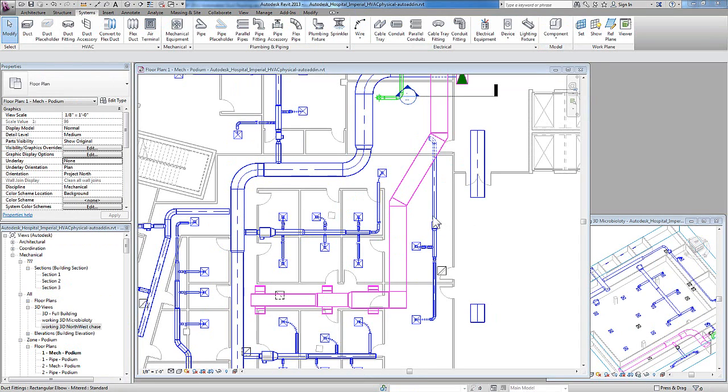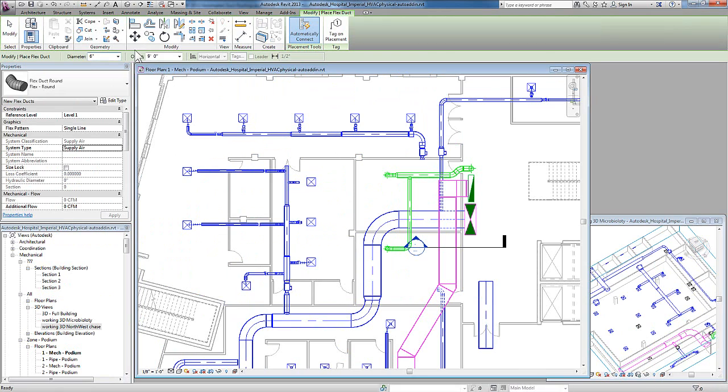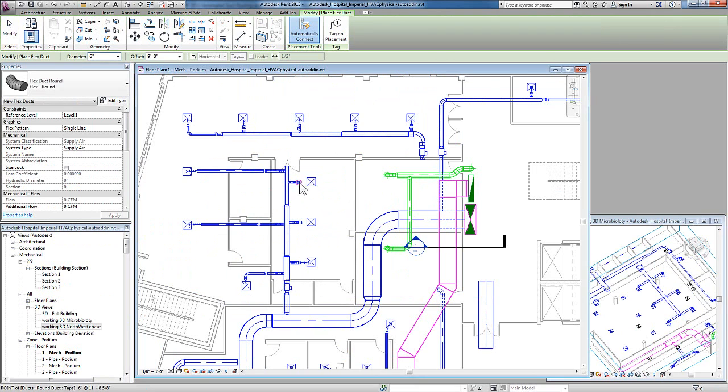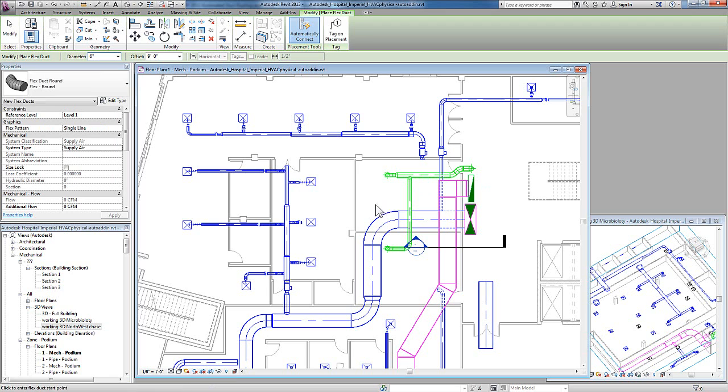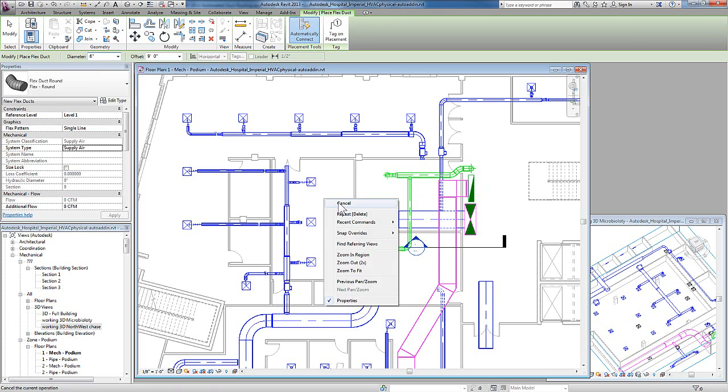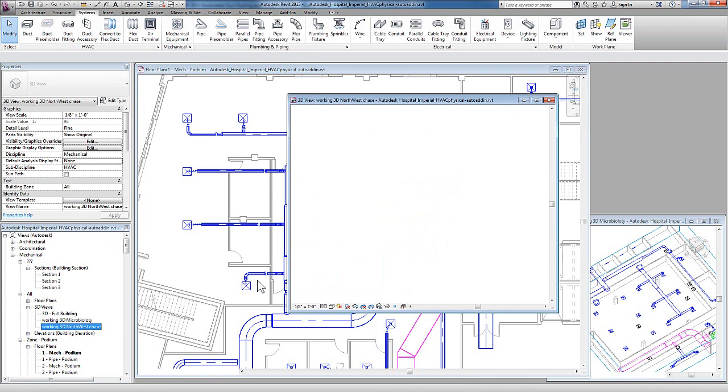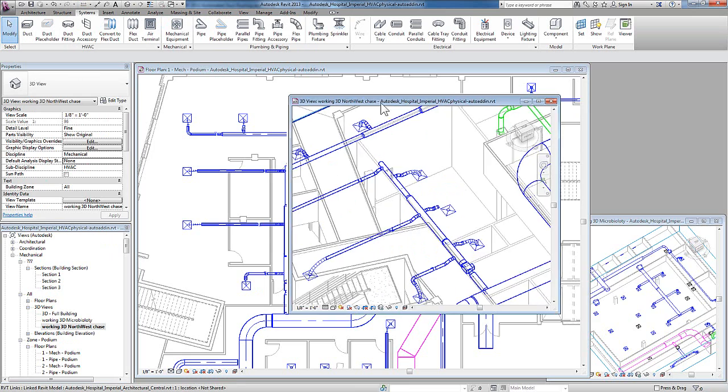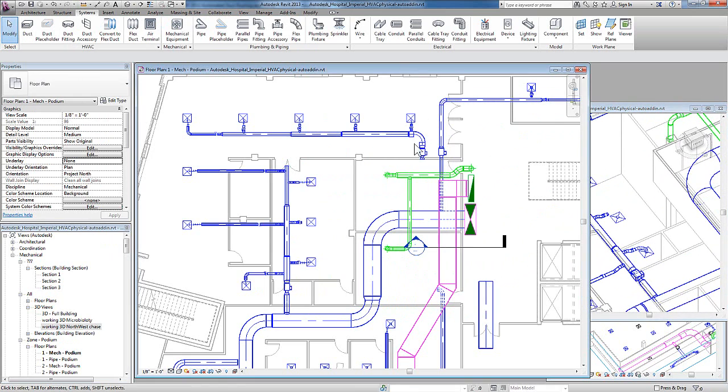If I want to manually add in flex ducts, I can use the flex duct tool and verify that the system type is correct and hover my cursor over the end of a duct, making sure that I'm hitting the connection point. Once I pick the connection point on the duct, I can pick the connection point on the terminal and the flex duct is automatically created in three dimensions, as well as in the plan view.